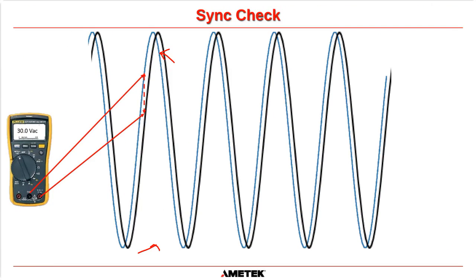And even if waveforms are only slightly out of phase, you can see here that the phase difference is only a very small amount in electrical degrees. I don't know exactly what it is in this case, but remember, with a sine wave you have to measure differences at any single point in time, and that's what this is doing here. There is a voltage difference of approximately, what did I say, about 30 volts between this point here on the inverter and this point here on the bypass. So if you put your Fluke meter's red cable on the live or the hot of the inverter, and your black cable on the live or hot of the bypass, you will measure about 30 volts AC.